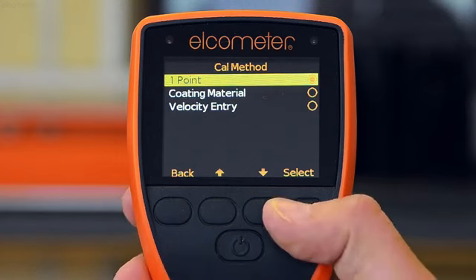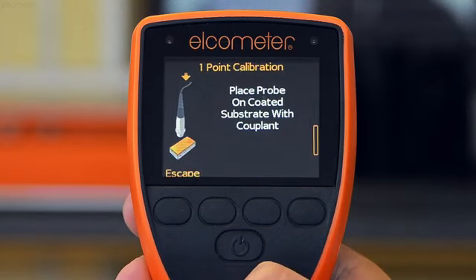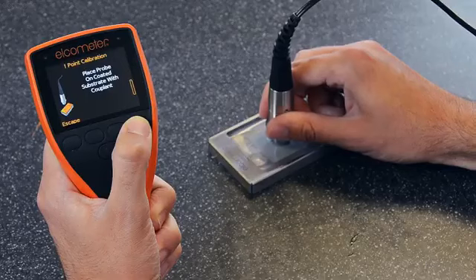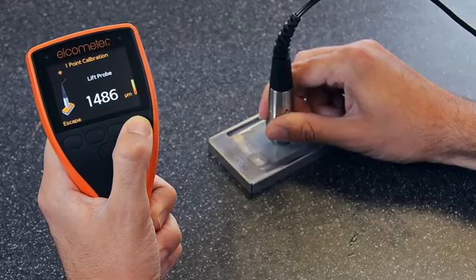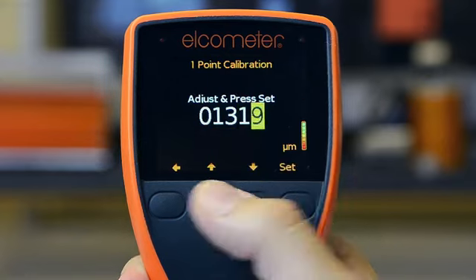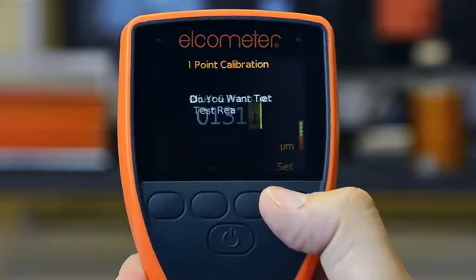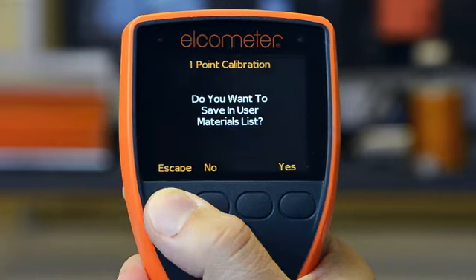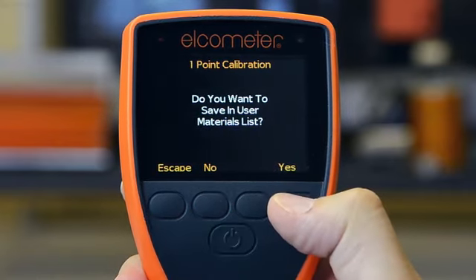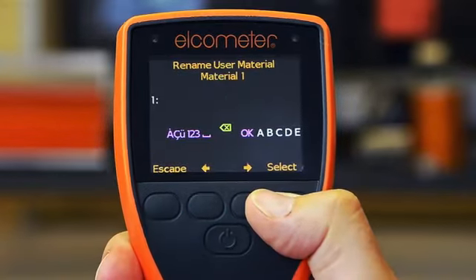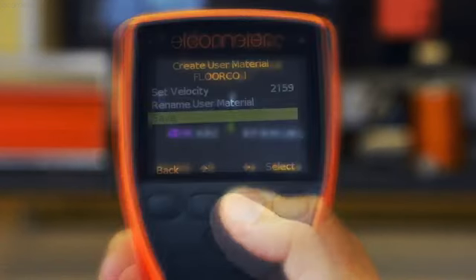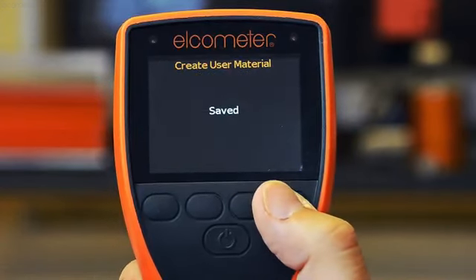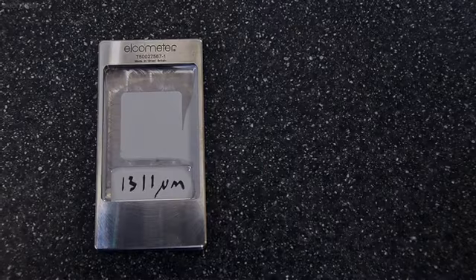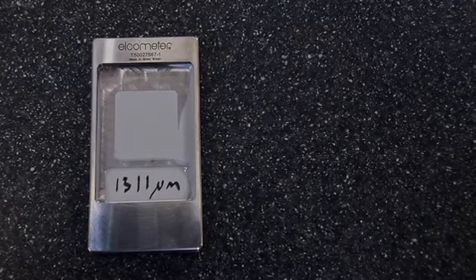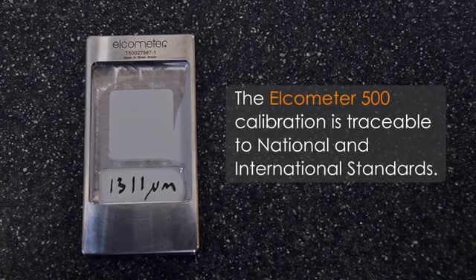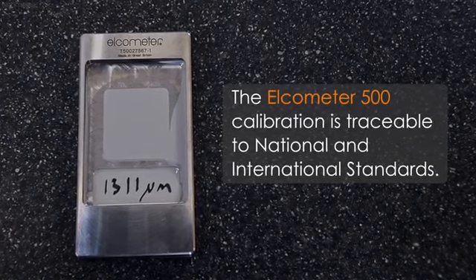Select the one-point calibration method from the Elcometer 500's calibration menu. Take a measurement of the coating at the same central point as the coating thickness gauge, and enter the dry film thickness value when prompted. Then press set. Again, the gauge will ask you if you wish to add this to the coating material library. To do so, press yes, and insert an appropriate name for the coating. The material name and speed of sound, or velocity, is now saved for use at any time. By using the Elcometer CCM in this way, the Elcometer 500 calibration is traceable to national and international standards.